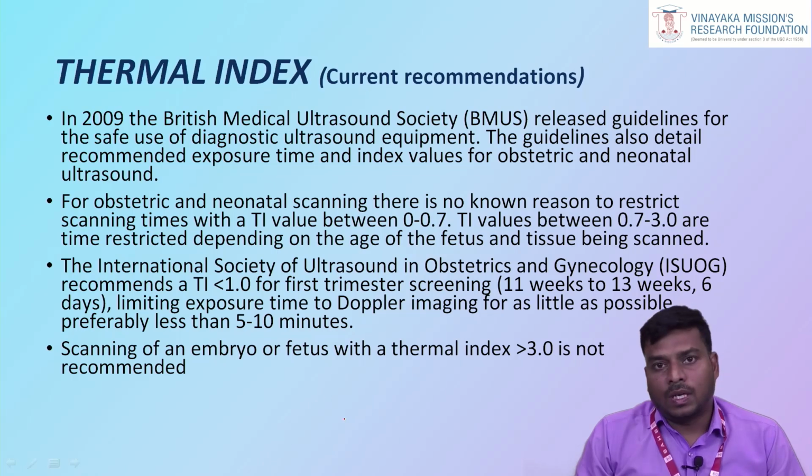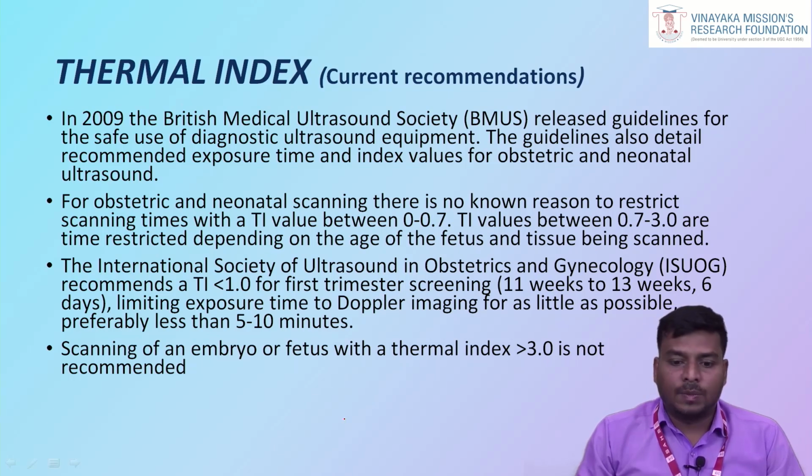Biological effects on the tissue are particularly relevant to the fetus. The International Society of Ultrasound in Obstetrics and Gynecology recommends a TI value less than 1.0 for first trimester scanning, which is 11 weeks to 13 weeks, 6 days. Limit the exposure time for Doppler scanning as much as possible, preferably to less than 5 to 10 minutes.